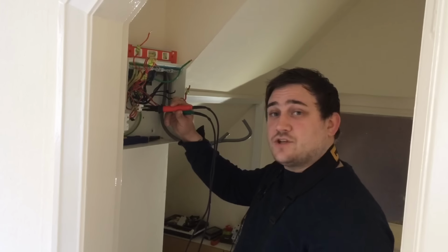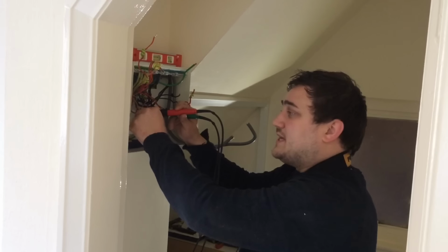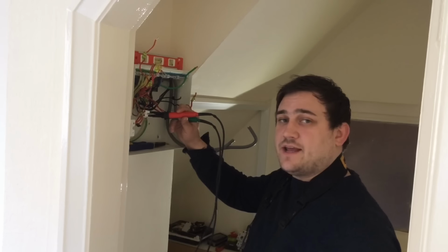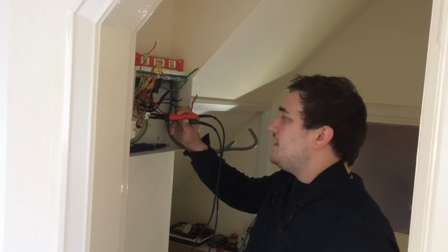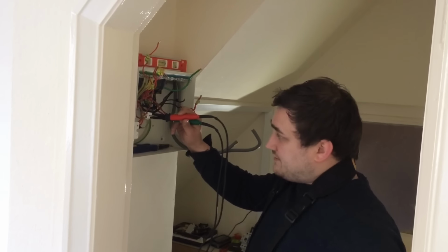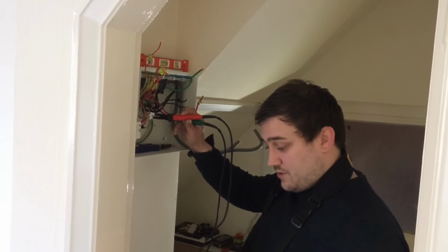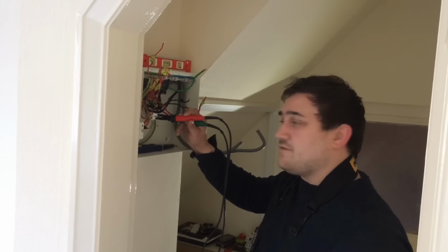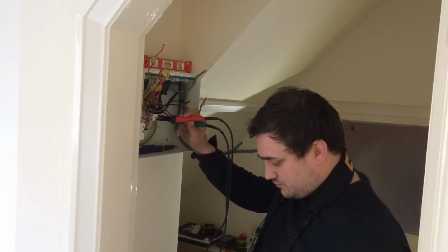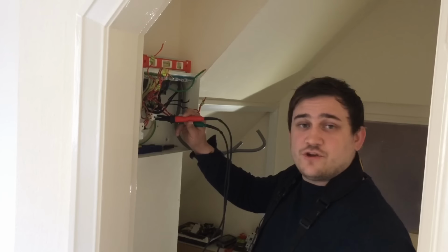They're zeroed. After zeroing my leads, I've come back to the consumer unit where I've now linked my opposite line and my opposite CPC together in a connector block, as I did with the line and neutral. I'm going to test in the consumer unit first, just to prove that my reading is within the 0.05 of my calculated reading of 0.15. I've got 0.12, so it is.